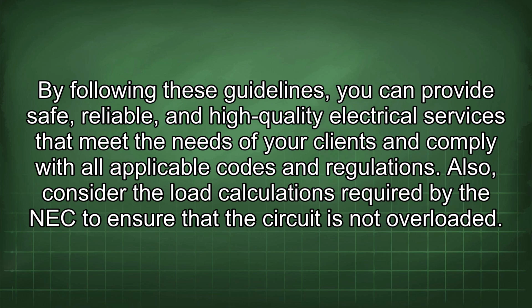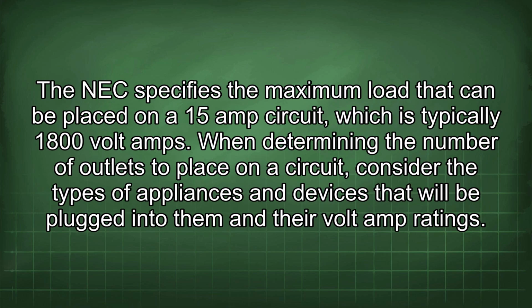Also, consider the load calculations required by the NEC to ensure that the circuit is not overloaded. The NEC specifies the maximum load that can be placed on a 15 amp circuit, which is typically 1800 volt amps. When determining the number of outlets to place on a circuit, consider the types of appliances and devices that will be plugged into them and their volt-amp ratings.